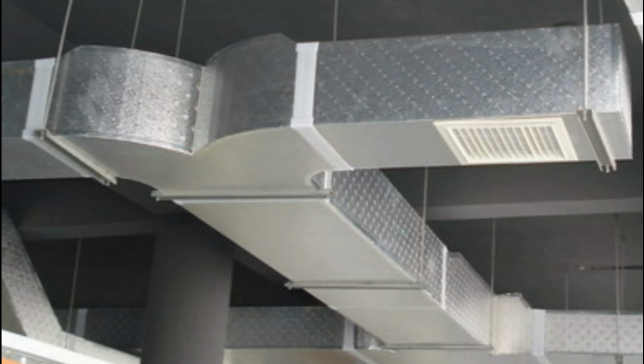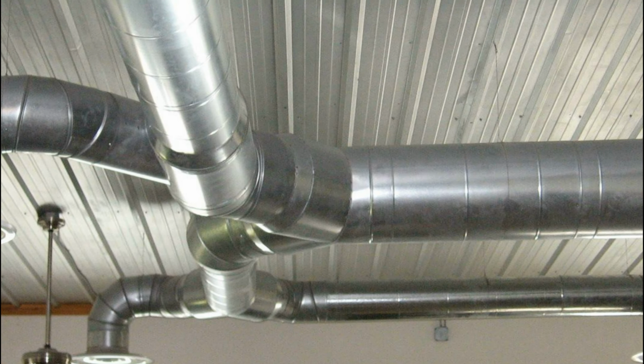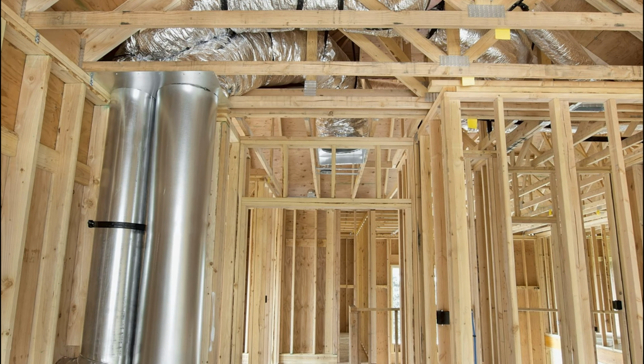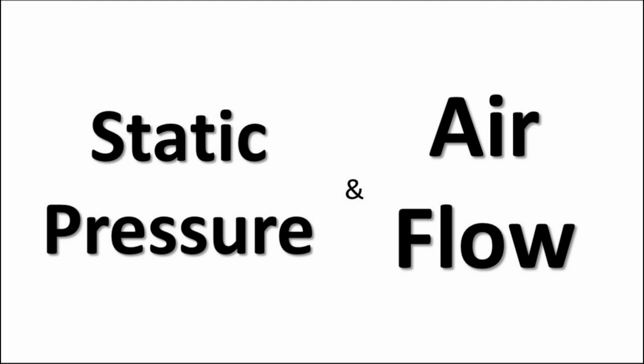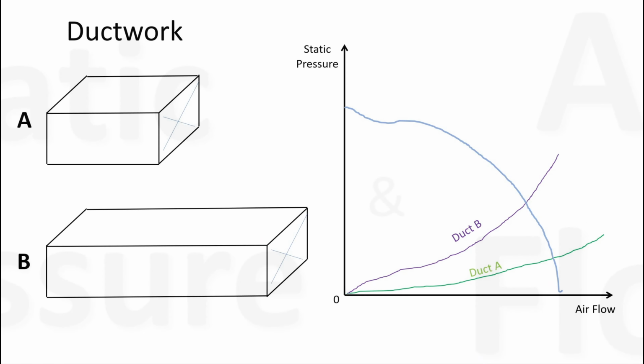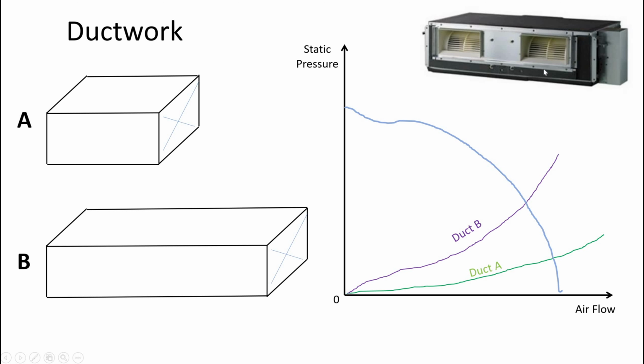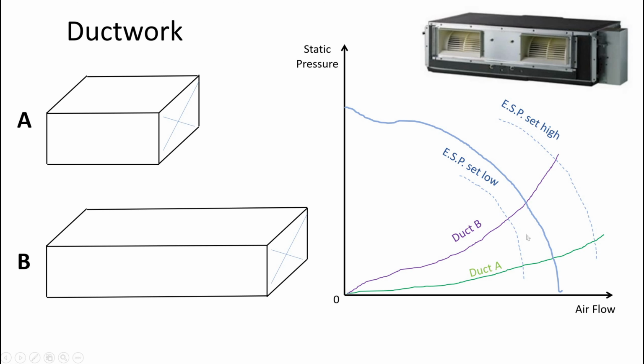When engineers design ductwork, they take into account duct size, number of turns, and a lot of other variables and constants. That is why it is very important to know airflow and static pressure before we start setting ESP. Let's summarize what we just talked about. First of all, a proper indoor unit needs to be selected to cover required loads, airflow, and static pressure. Each ducted type indoor unit has a range for setting airflow and static pressure. From the factory, it comes with ESP set to high. Let's say ESP is not set for the designed ductwork values.